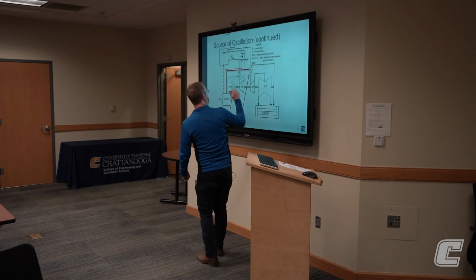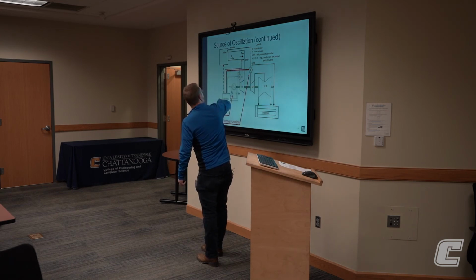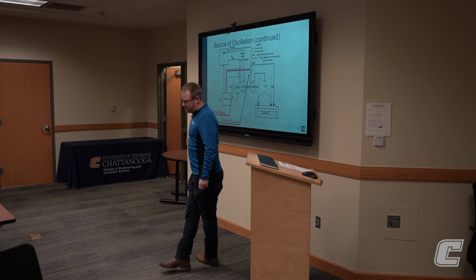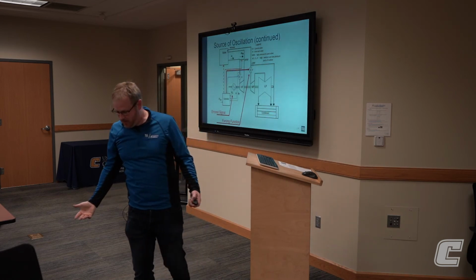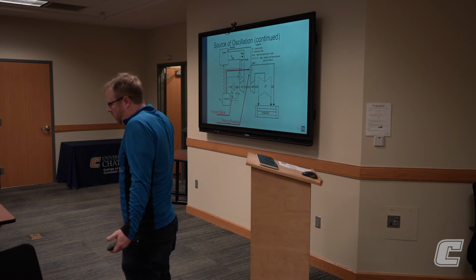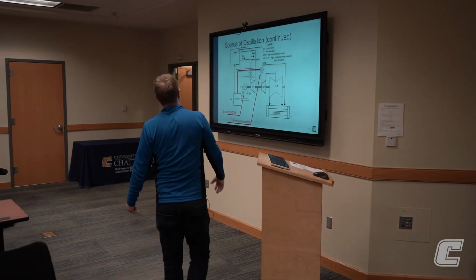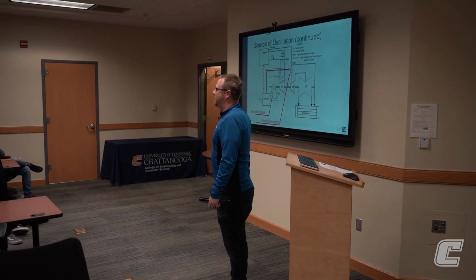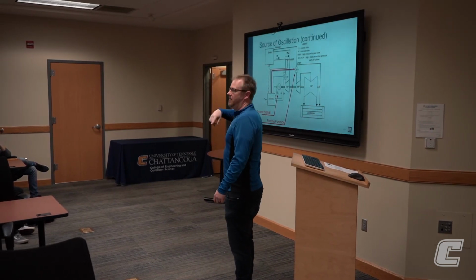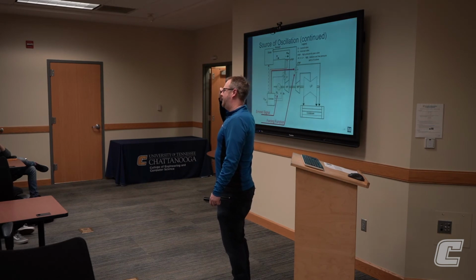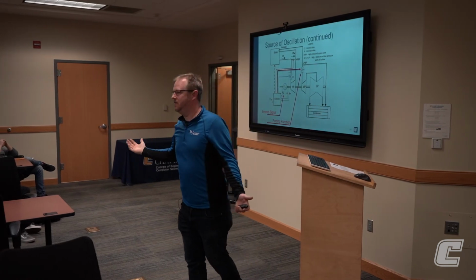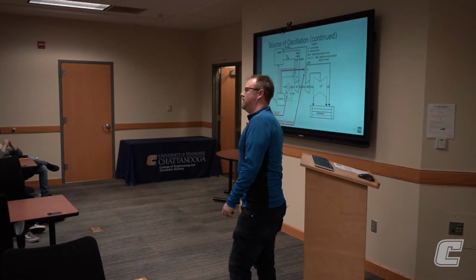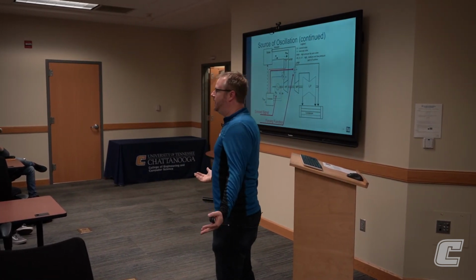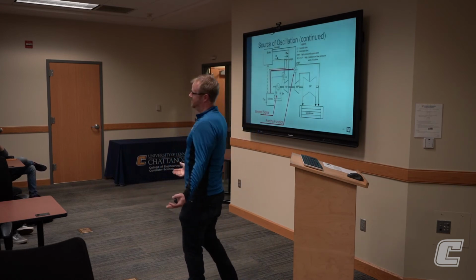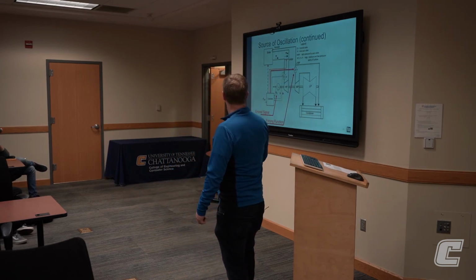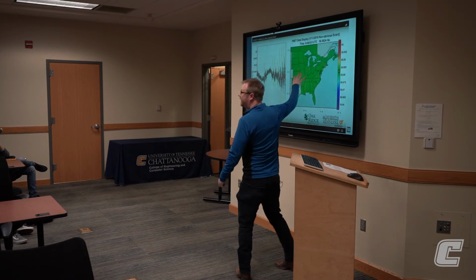Yes, this power load imbalance, wherever it's at here, feeding into this controller, it had lost its voltage signal. So again, it didn't have a reference, and it was trying to control the output of the unit, and it didn't know what reference signal. It didn't have a great reference signal because it lost one of the phase values. So it started oscillating up and down, megawatts going up and down, and people were like, "Oh, that must have been a huge unit, 1,000 megawatt unit." Nope, it was a 200 megawatt unit, which is not small, but compared to some of our bigger units, nuclear units, that is small. This little unit was swinging the whole grid.